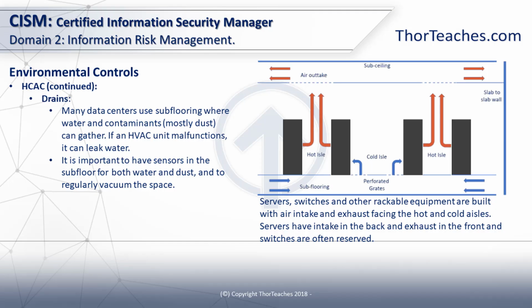So on the front side of the racks, we push cold air in, and we do this by having perforated grates in the floor, so the cooled air pushed in by the air conditioners can only exit in the cold aisles, where all the servers take the air in. Then at the back of the racks, all the servers push the air out, and we have air outtakes at the top, above that, where the air is pulled out through the AC unit. And that's really how we cool our data center.